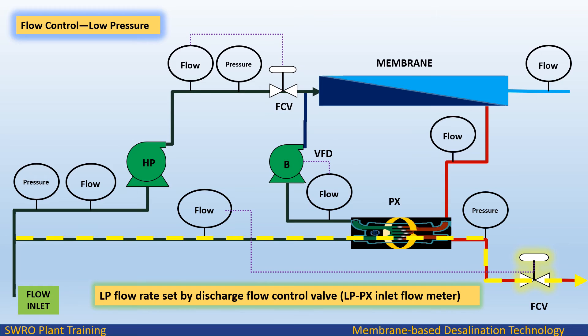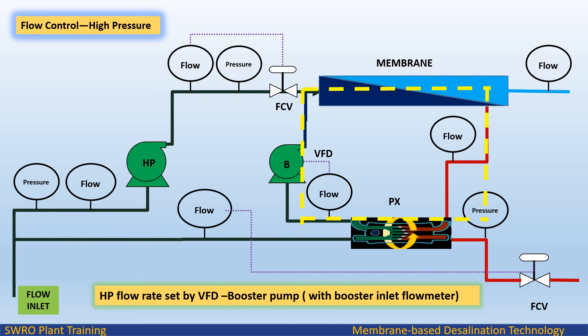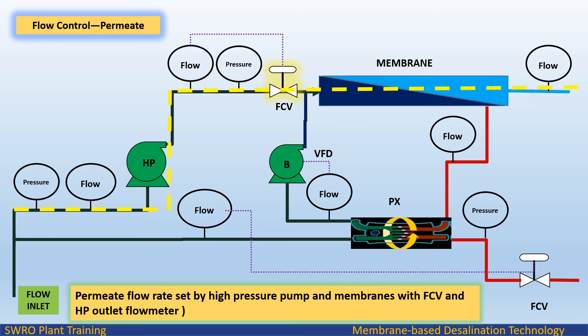RO process control — low pressure: flow rate is set by a discharge flow control valve at the brine outlet line, using the inlet LP PX flow meter set point. RO process control — high pressure: PX flow rate is set by the VFD booster pump with the booster inlet flow meter. RO process control — permeate: flow rate is set by the high pressure pump and membranes with FCV and HP outlet flow meter.